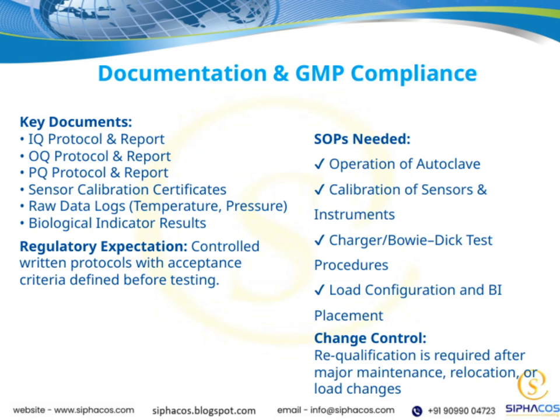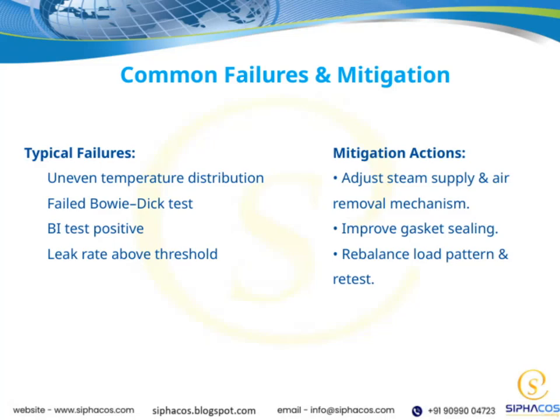Finally, when it comes to change control, requalification becomes necessary after any major maintenance, equipment relocation, or significant load changes. This ensures that the sterilization process remains validated and reliable, maintaining the overall integrity of our sterilization program. Now, let's look at some key mitigation actions that can really make a difference. First, adjusting the steam supply and the air removal mechanism helps ensure proper sterilization conditions and prevents issues caused by inadequate steam or air pockets.